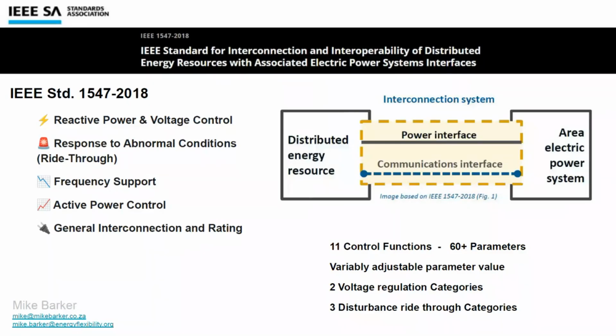A standard called 1547. It's been around since 2003, and before that even the guys were working on that. And it really spells out two different paths to connecting your DER, your inverter, to the feeder, to the grid. So first of all, the physical interface, which is the transfer of power backwards and forwards, and then a communications interface as well. Now, I'm not going to look at the communications interface, I don't think we're quite there yet, and I've only got a limited amount of time.